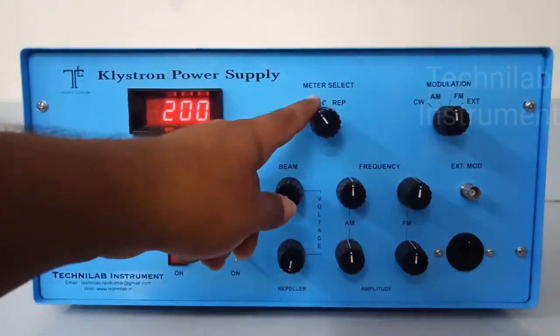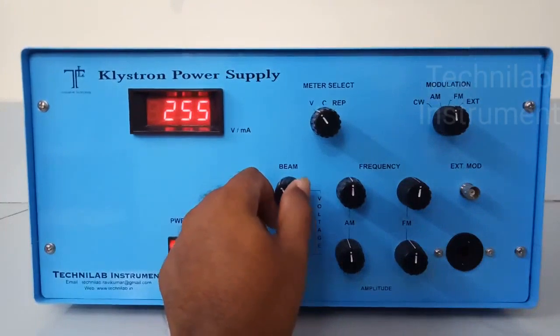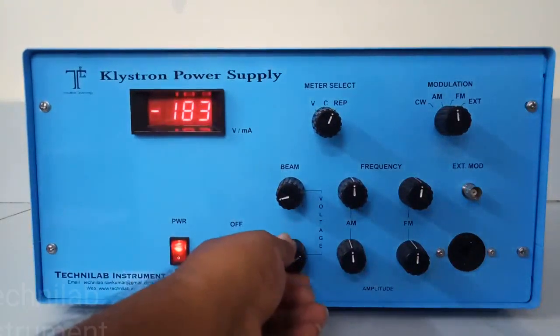Here is the meter selection switch. The first position is beam voltage, the second is beam current, and the third is repeller voltage. There is only one display for all three — we have to read all three by selecting the switch. Whatever position you keep the switch, that value will be displayed on the 7-segment display. Currently it is showing beam voltage: 200 volts. I can vary this voltage up to 450 volts. Since the output is not connected to any load, there is no current right now. And the repeller voltage — up to 270 V, currently showing 267 V. It is also variable.